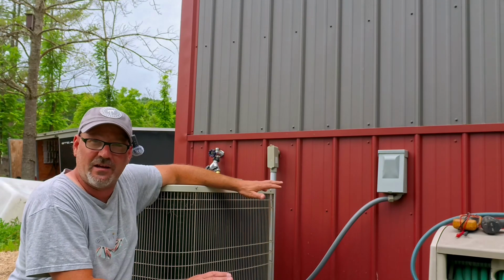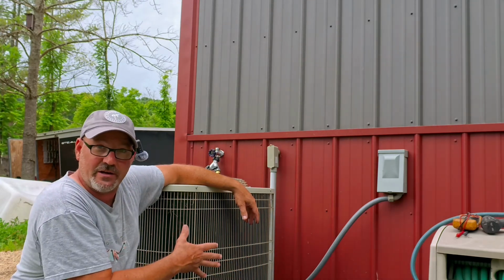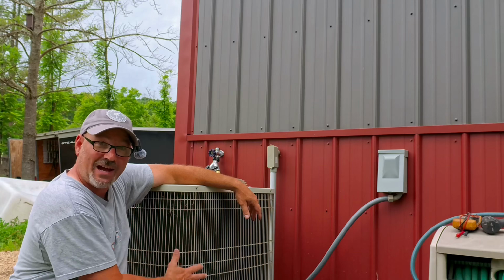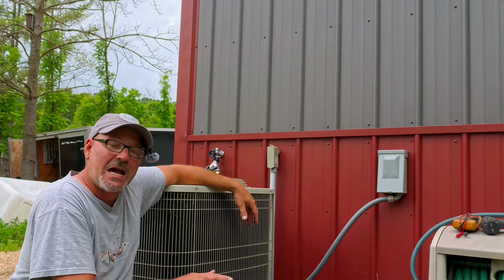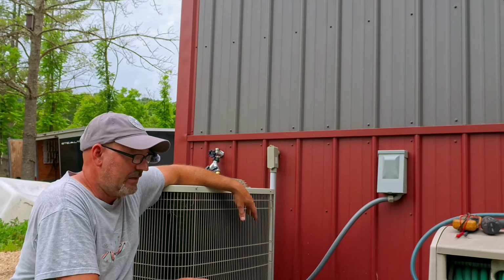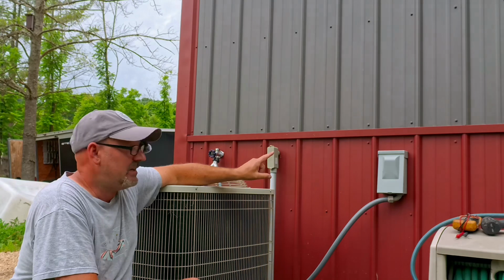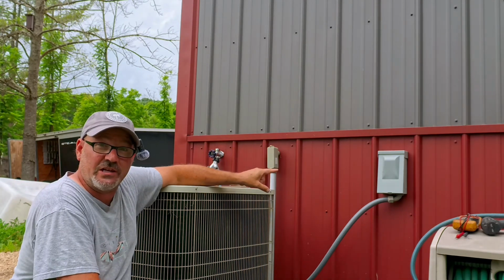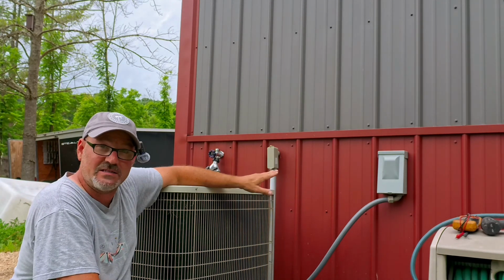Now, if you live in the Midwest like we do, and you have the cottonwood flying all over the air in the springtime, it's natural for it to get sucked right into this air conditioner and build up a nice layer of cotton right across the front of this machine. If you stay on top of it, it's easy to remove. The easiest way to do that is simply with a water hose. But first, pull the disconnect and shut the unit off. If you don't have a disconnect outside, go to the main breaker and shut the breaker off.